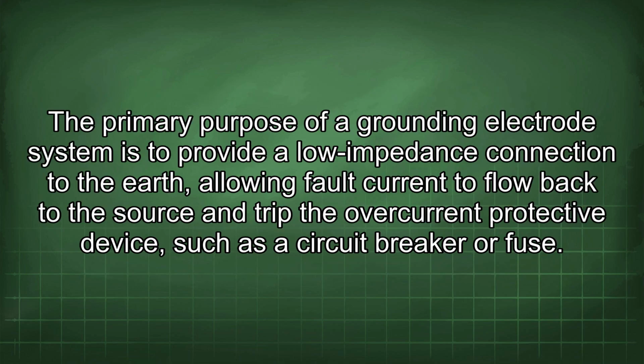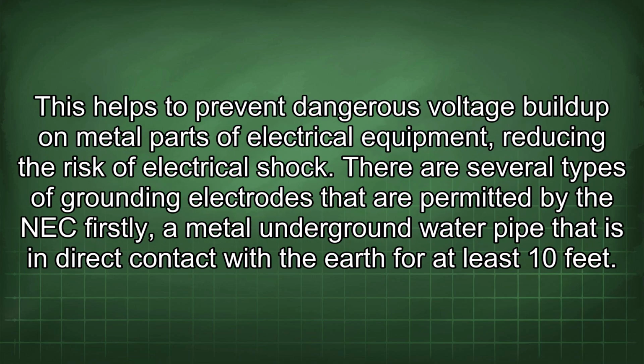The primary purpose of a grounding electrode system is to provide a low impedance connection to the earth, allowing fault current to flow back to the source and trip the overcurrent protective device, such as a circuit breaker or fuse. This helps to prevent dangerous voltage buildup on metal parts of electrical equipment, reducing the risk of electrical shock.